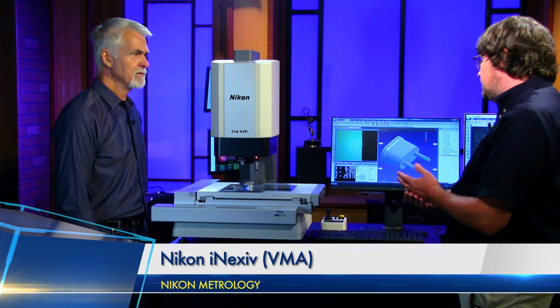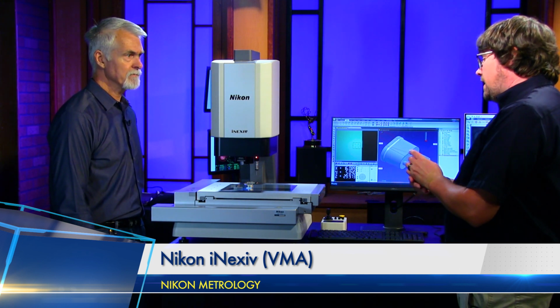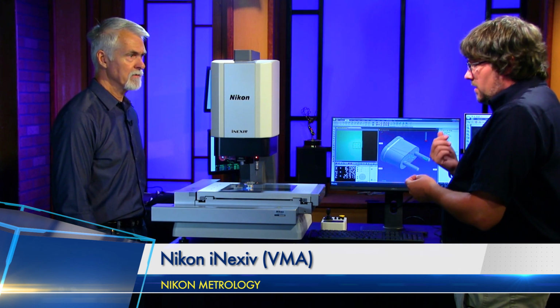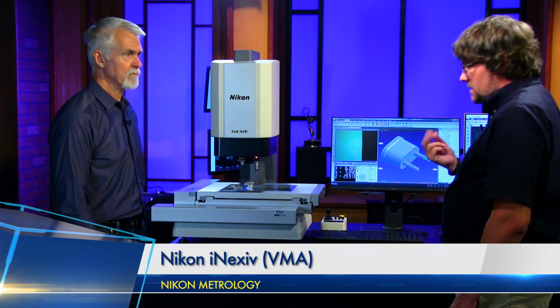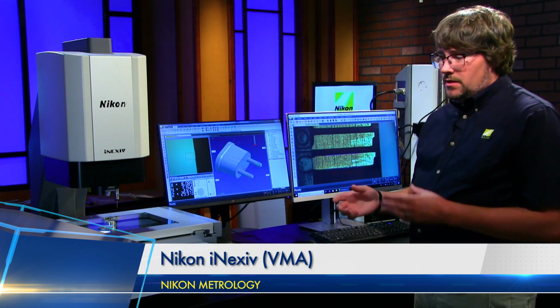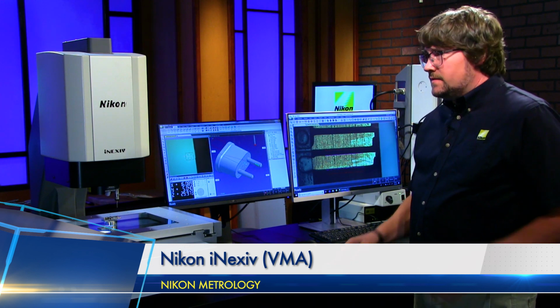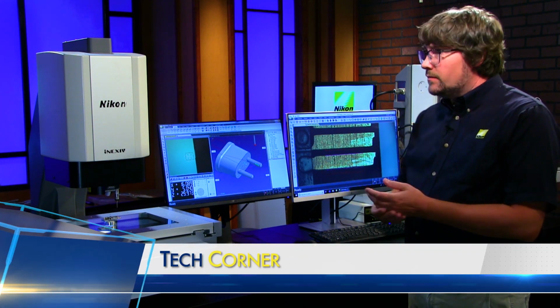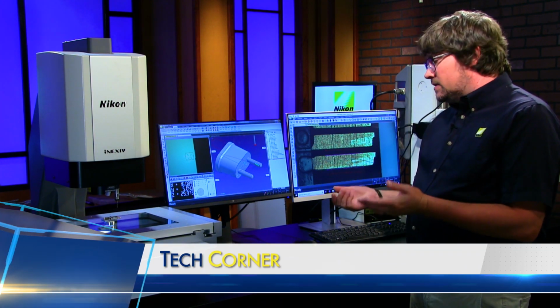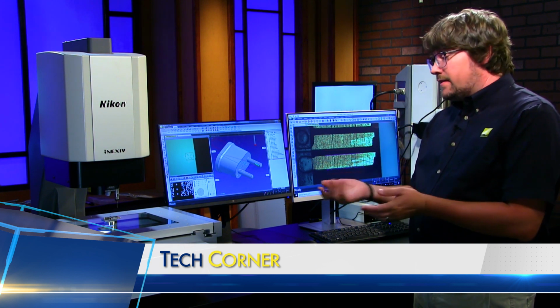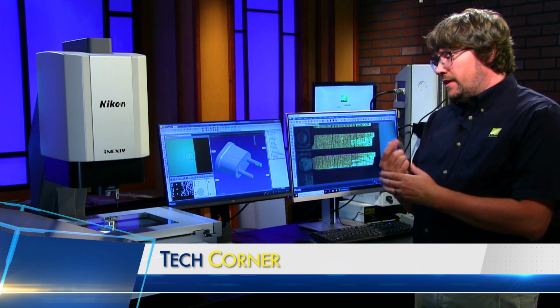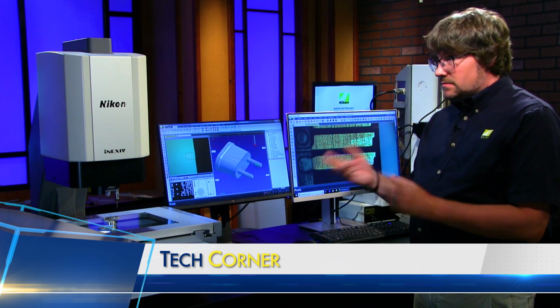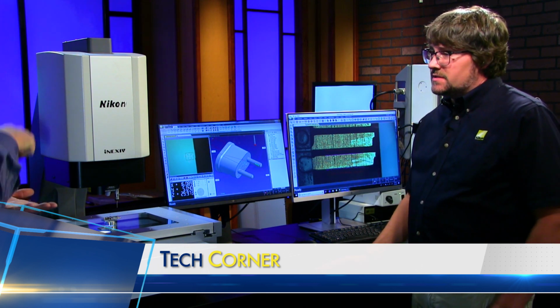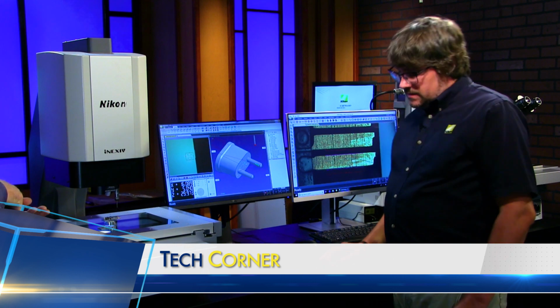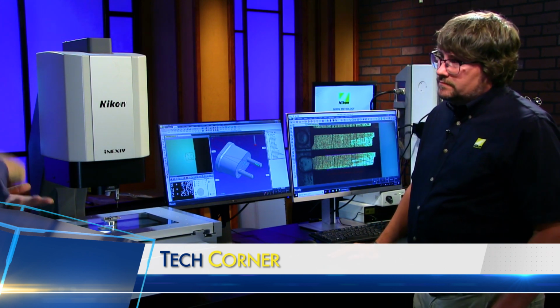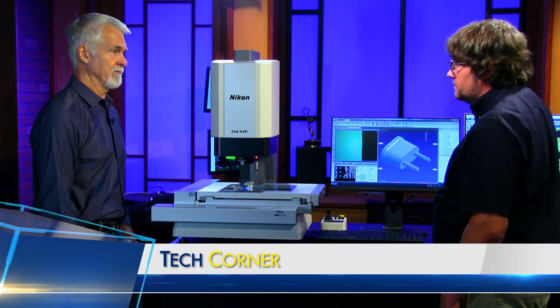Yeah, so that's all accounted for. There's a calibration that can be performed that correlates the vision probe, the touch probe, and the laser probe, all within the entire volume of the CMM, or of the vision system. Okay. So that's built-in functionality to the software. There's an artifact included with these that will calibrate the vision probe and also do this cross-calibration between them. And you said earlier Z-axis measurements are also possible, I'm assuming with the touch probe and with the vision. Yes, of course.